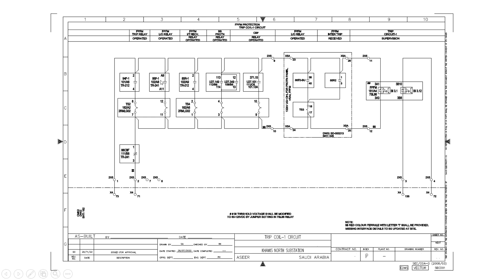When 86F operates, this is the lockout relay. A lockout relay, once operated, will continuously make its contacts until manually reset. So the continuous positive pulse will extend to the trip coil.